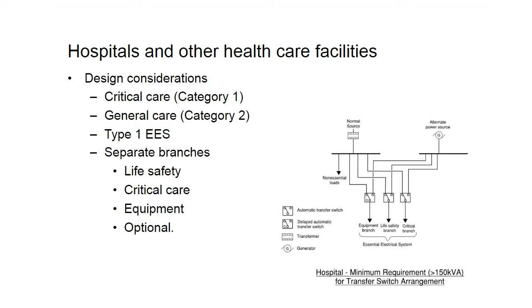The entire system, both normal and emergency, shall be designed to minimize interruptions. Obviously, we want to keep power to the most critical components of both of these facility types. Many hospitals are oftentimes looking for what I'll call near normal operating conditions in some parts of their facility, so they really don't experience any type of impact or minimal impact when they're operating on generator power.